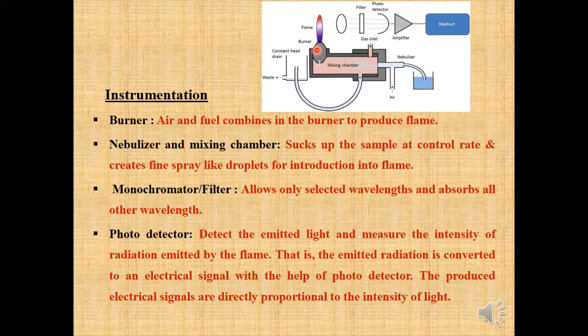The radiation from the flame passes through a lens and to the filter. The role of the filter is to allow only the specific wavelength and to absorb all other wavelengths. Next, it is passed through the photo detector, which detects the emitted light and measures the intensity of radiation emitted by the flame. The emitted radiation is converted into an electrical signal with the help of the photo detector. Next, it is amplified, processed, and passed through the readout.